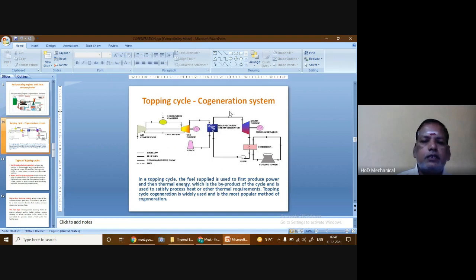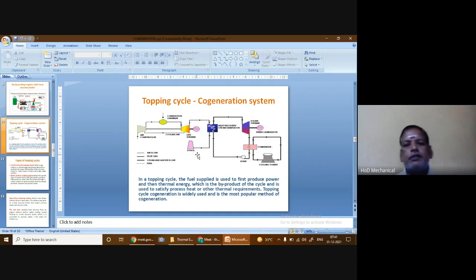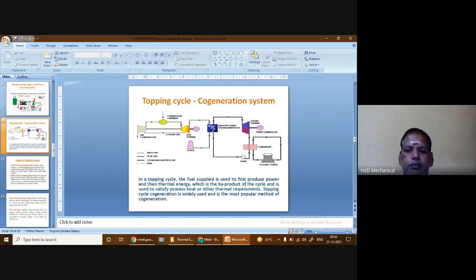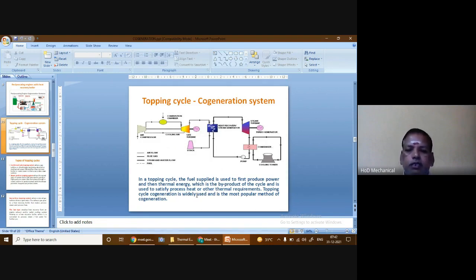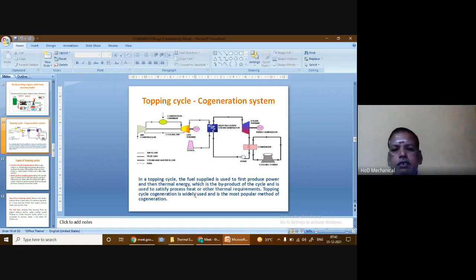This is called the topping cycle cogeneration. In a topping cycle, the fuel supplied is first used to produce power, and the thermal energy — which is the byproduct of the cycle — is used to satisfy process heat or other thermal requirements. Topping cycle cogeneration is widely used and is the most popular method of cogeneration, employed in all thermal power stations as well as gas turbine power stations.